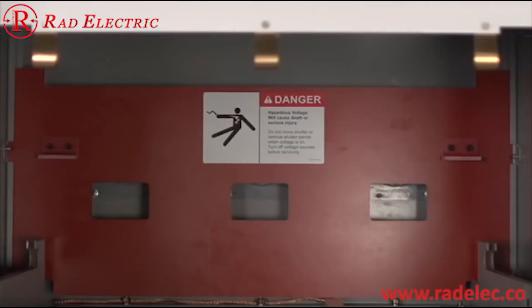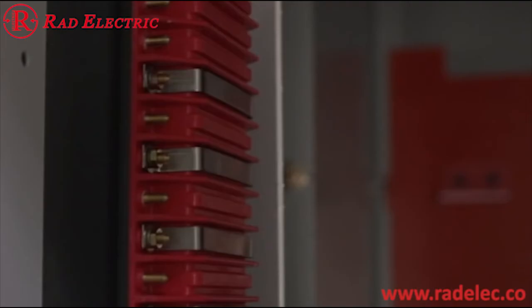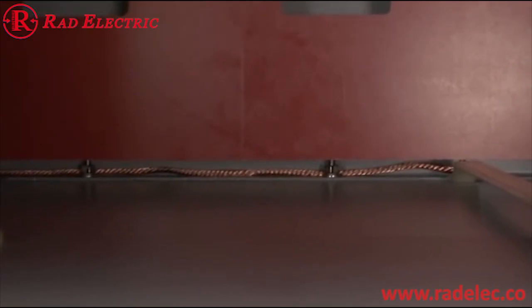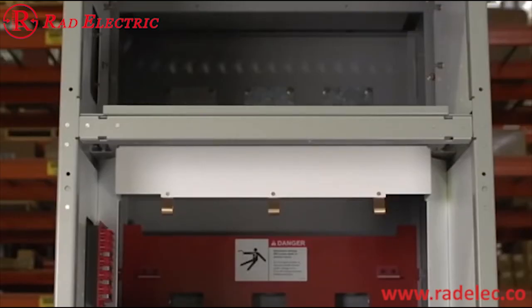This is the auxiliary voltage transformer compartment. If the compartment is utilized, the extension rails are the exact same as those on the lower compartments and are also the exact same for trays and circuit breakers. Extension rails are used to facilitate the insertion of the tray into the compartment and allow for complete withdrawal from the cell. On the left, we have the secondary disconnect terminals for secondary wiring. As the tray slides in, these connect. On the top, we see the ground contact system, which removes static charges from the instrument transformer or fuse. Underneath the tray, we have the grounding system. This top compartment is the C compartment. Typically, this compartment is connected to the runbacks by a cable.